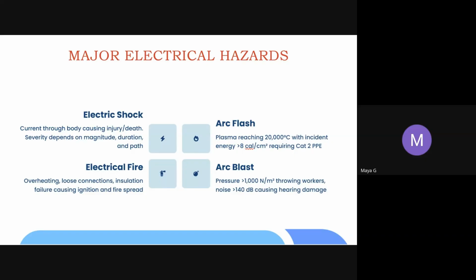Arc flash. When an arc flash occurs, plasma reaching 20,000 degrees Celsius with incident energy greater than 8 calories per centimeter square will occur. Arc blast. It's a condition when the pressure increases and the copper expands quickly, throwing away the workers nearby, and the noise rises to more than 140 decibels, causing hearing damage.